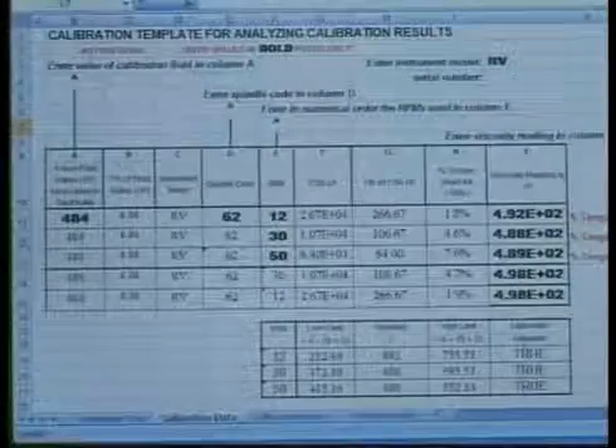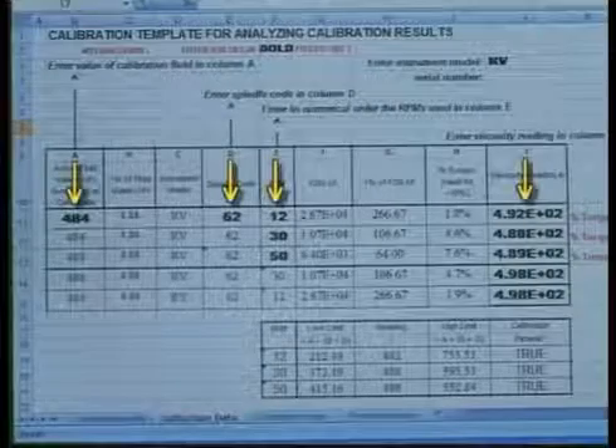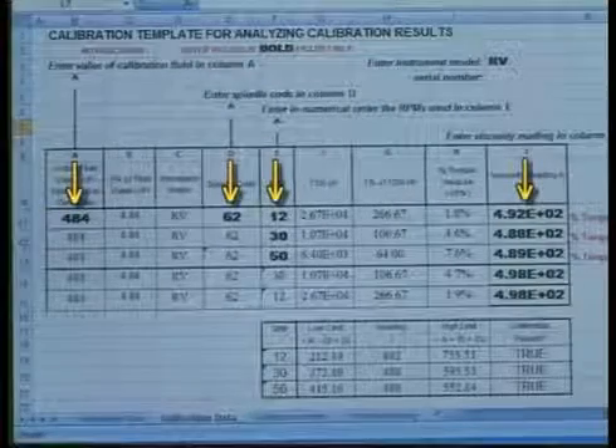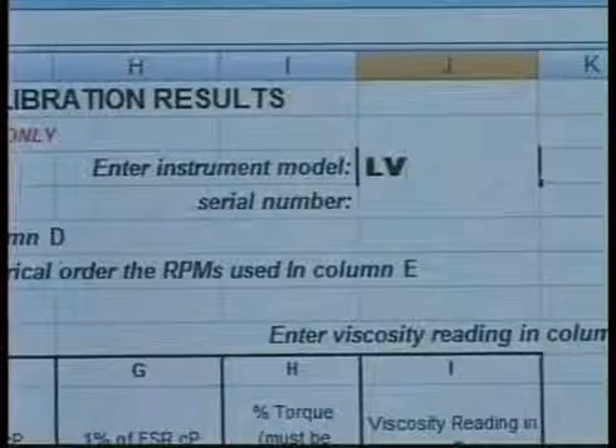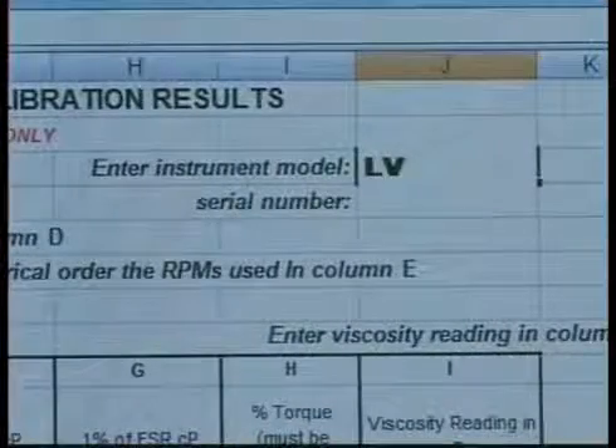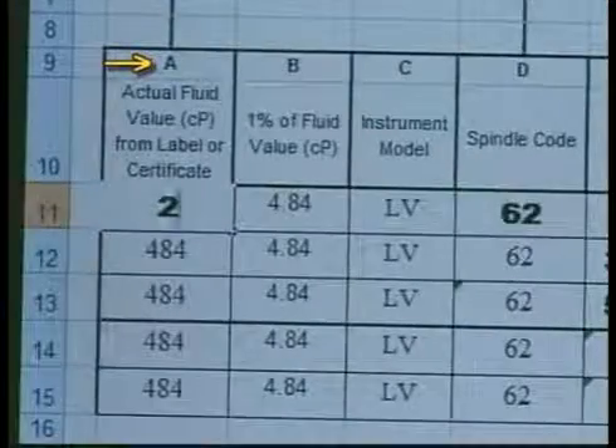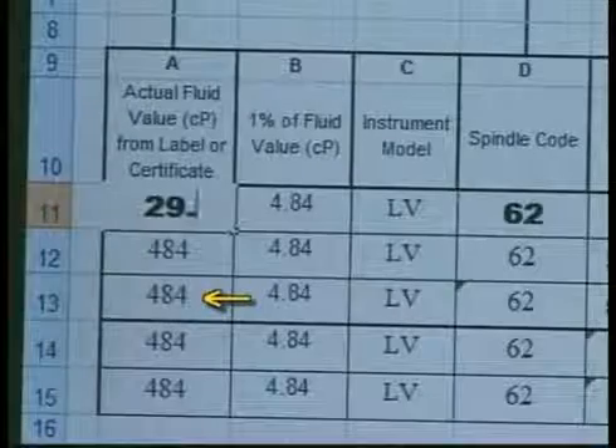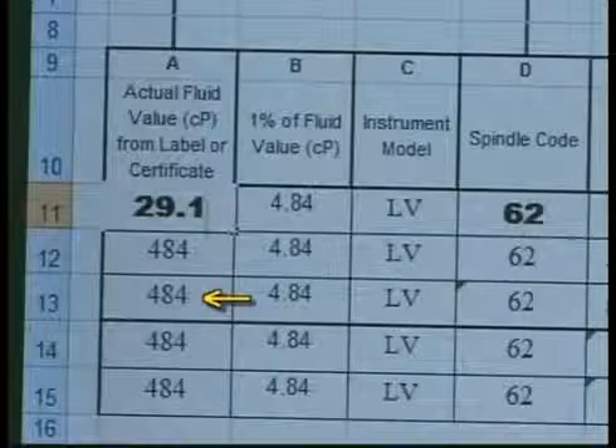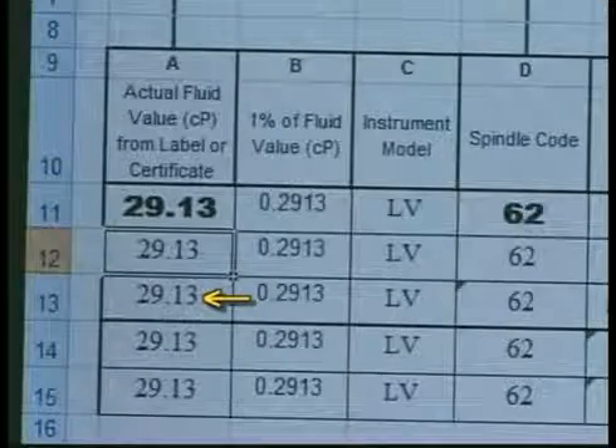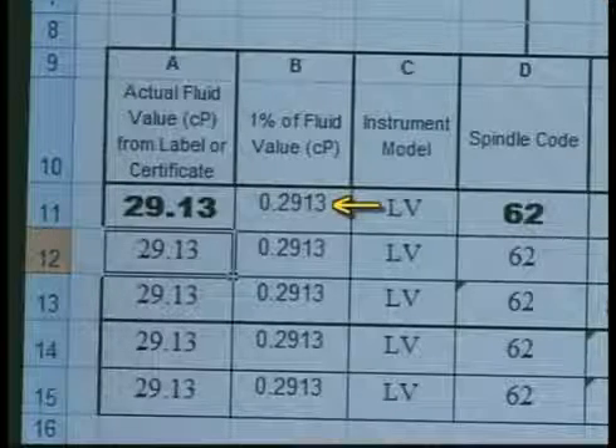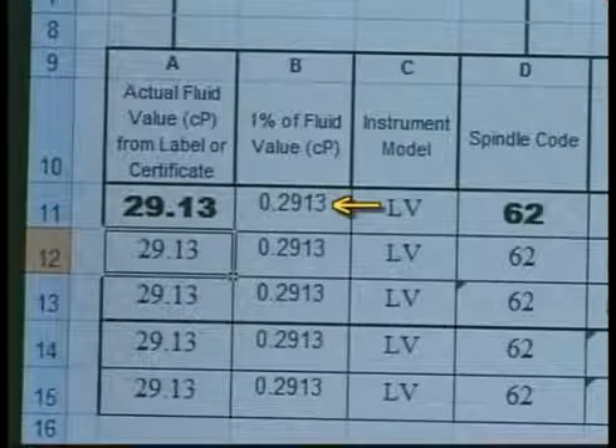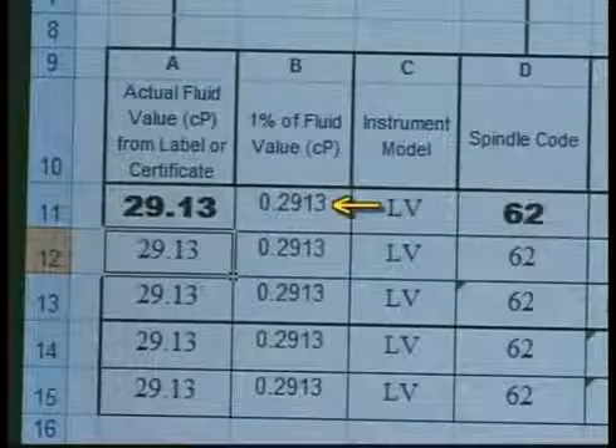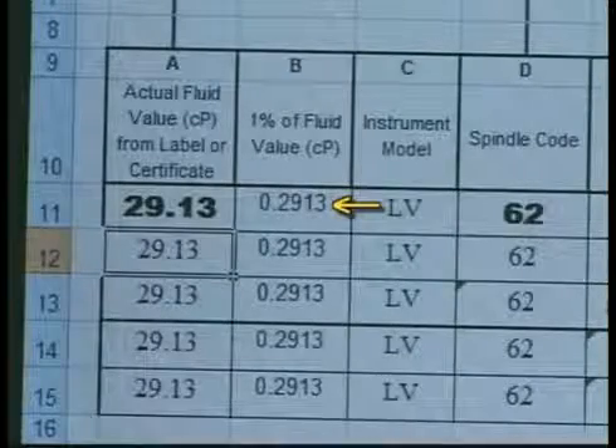To see what these tolerances mean, let's look at this calibration worksheet. Enter data in the bold fields. First, enter the spring torque of your instrument. In this case, this will be an LV. Enter the actual value of the fluid in column A. The remaining fields in this column will automatically update, as this value will not change. You can see the 1% fluid value column will update based on this entry. This is the accuracy of the fluid.